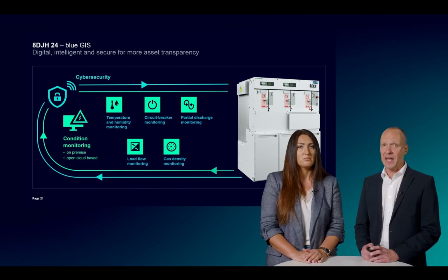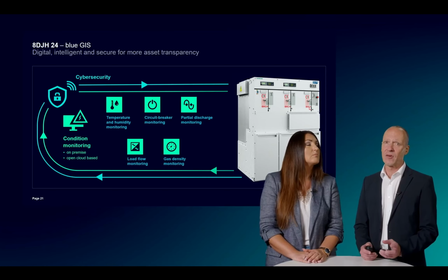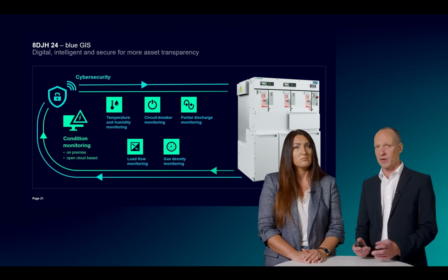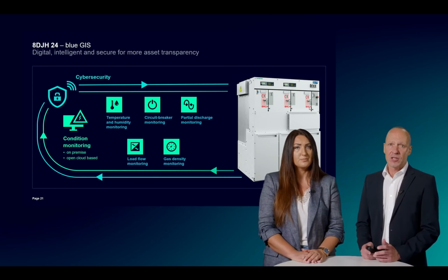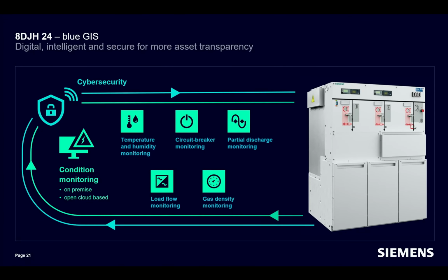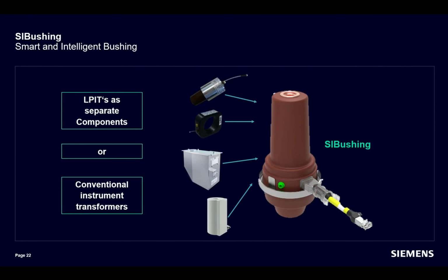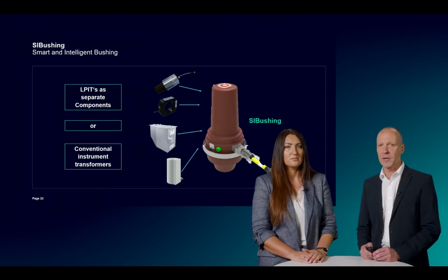As you may imagine, the space for possible sensor installation is there even more limited due to the compact design compared with the NX Plus C. Especially conventional voltage and current transformers or non-conventional alternatives, so-called low-power instrument transformers, which are required, for example, for load flow monitoring, can only be hardly installed in such compact ring main units. Therefore, I'm proud and happy that we have managed in the meanwhile to integrate the current and voltage measuring in our cable connection bushing with low-power instrument transformer technology.